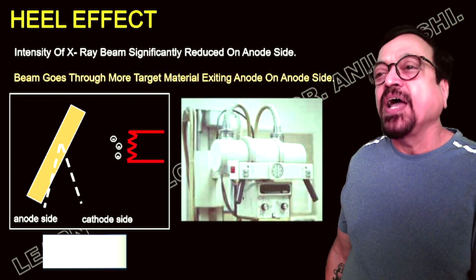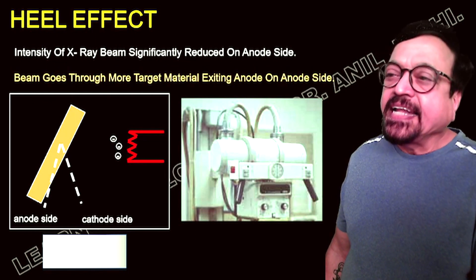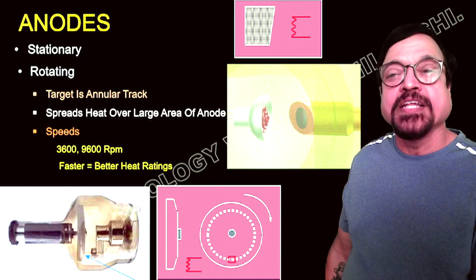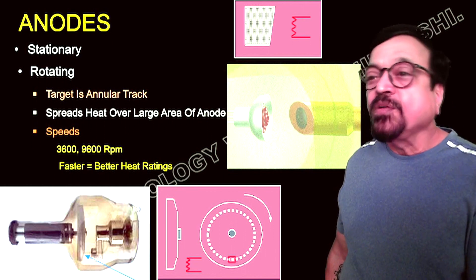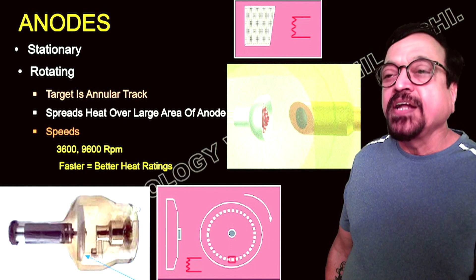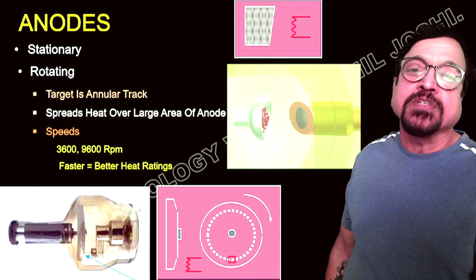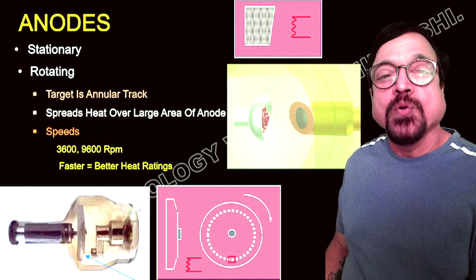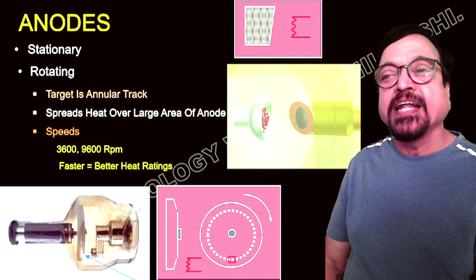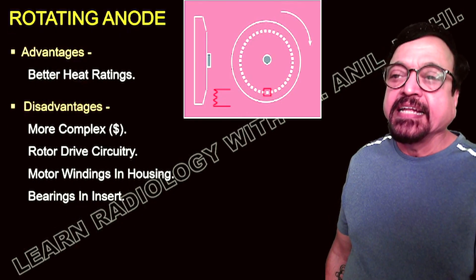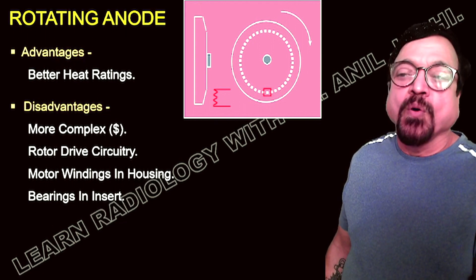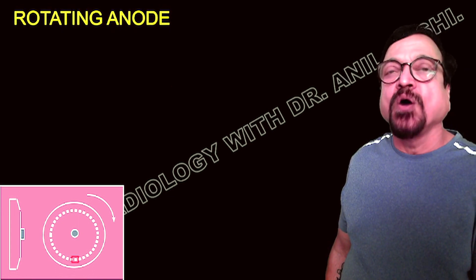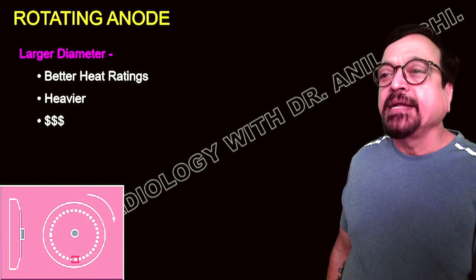The heel effect refers to the fact that the intensity of the x-ray beam is significantly reduced on the anode side, because the beam goes through more target material on that side. Anodes are either stationary or rotating. Stationary anodes are used in dental tubes; rotating anodes are used in routine radiographic departmental tubes. In a rotating anode tube, the target is an annular track that spreads heat over a larger area, allowing better tube ratings, more successive exposures, and higher mA. The anode rotation speed is between 3,600 and 9,600 RPM. Advantages of rotating anodes include better heat rating; disadvantages include more complex circuits, more complicated housings and bearings, larger and heavier design, and greater cost.